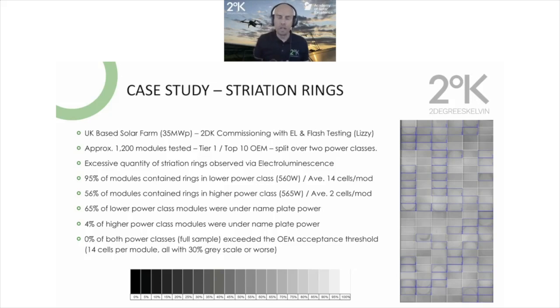We were commissioned to do electroluminescence and flash testing using our MBJ 5.0 Max, which is Lizzie. We tested around 1,200 modules from a tier 1 top 10 international module supplier, split over 2 power classes - 560s and 565s - and what we saw was an extensive quantity of these striation rings. We didn't really know much about it at the time, but we did some research.